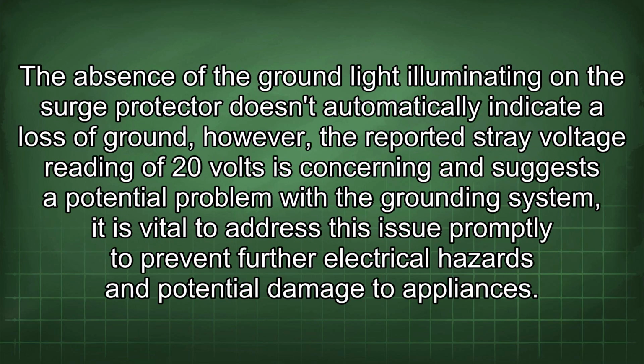The absence of the ground light illuminating on the surge protector doesn't automatically indicate a loss of ground. However, the reported stray voltage reading of 20 volts is concerning and suggests a potential problem with the grounding system. It is vital to address this issue promptly to prevent further electrical hazards and potential damage to appliances.